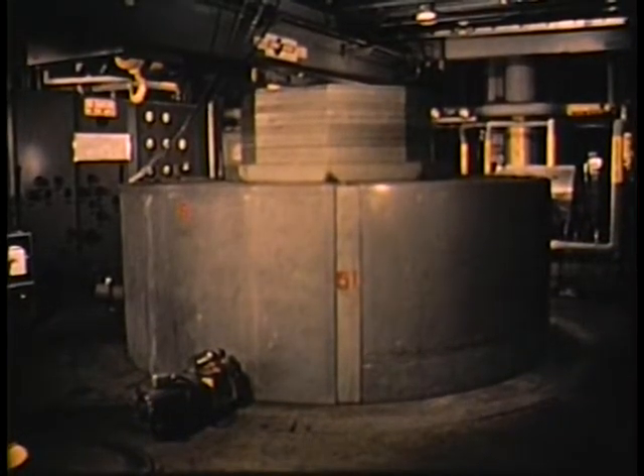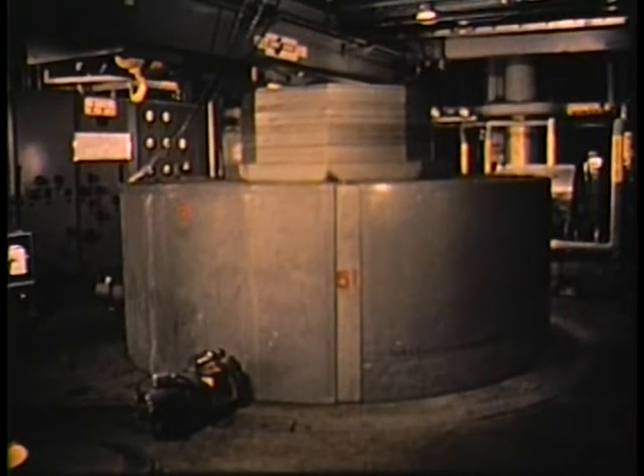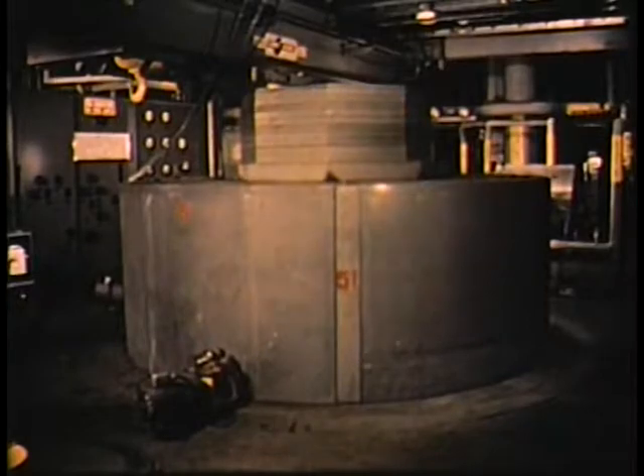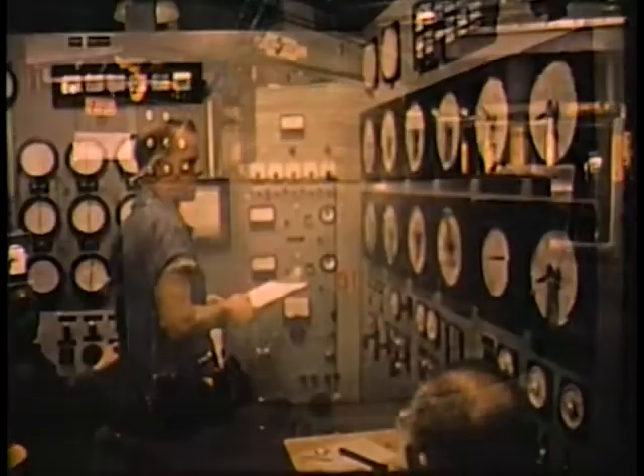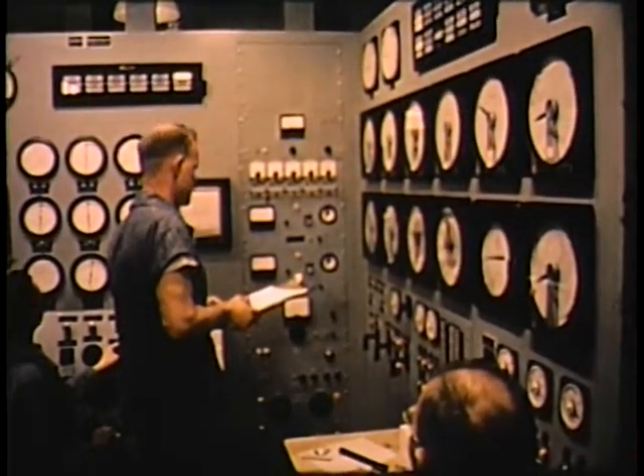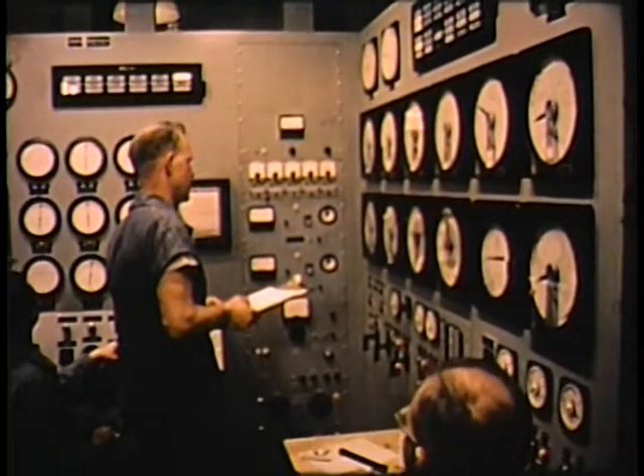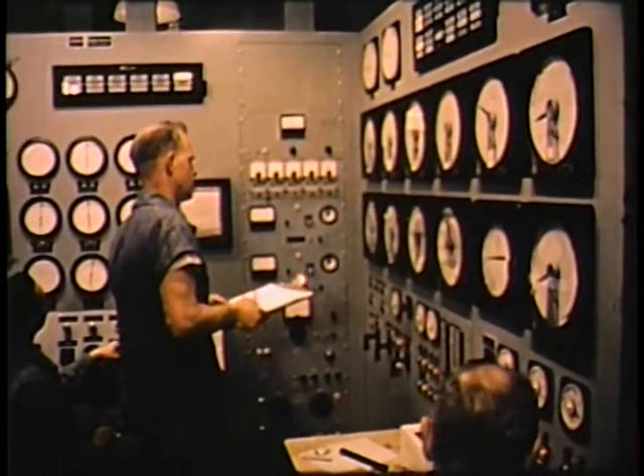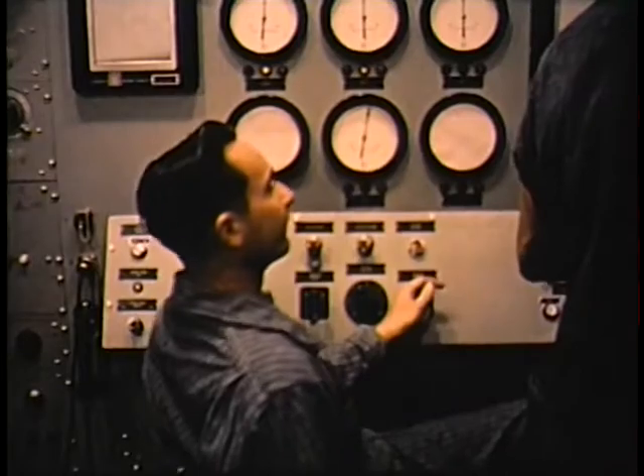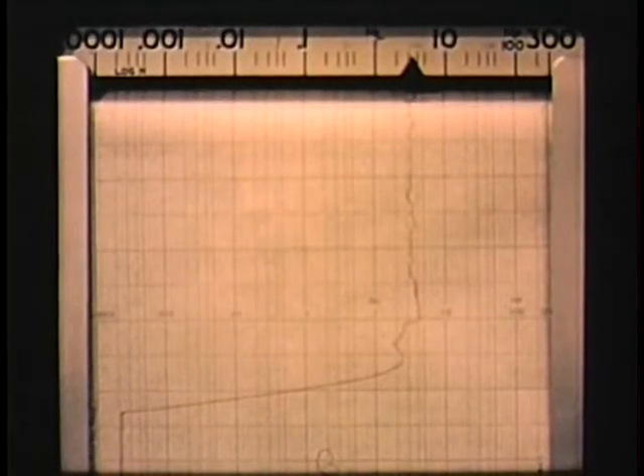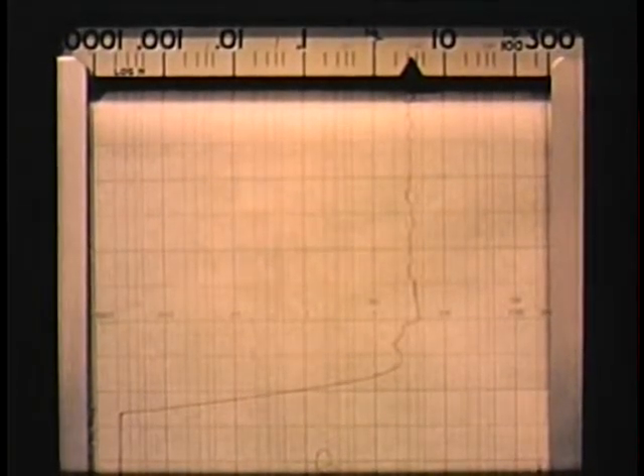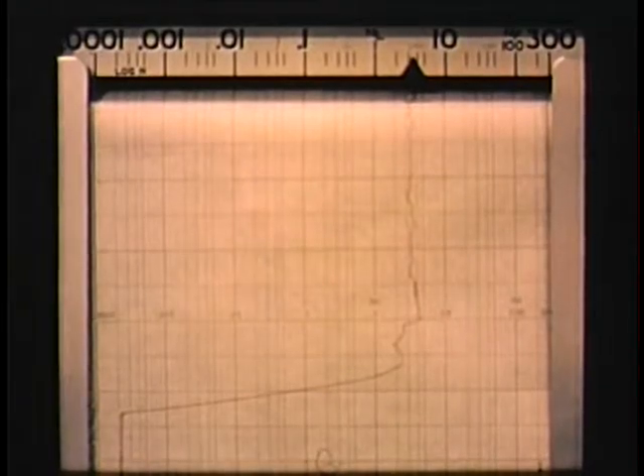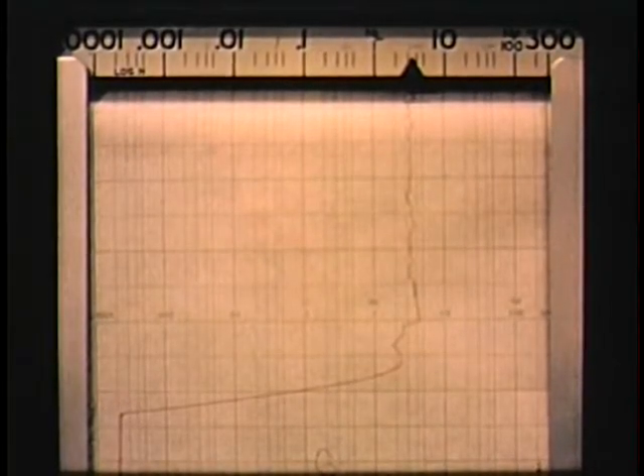On October 23, 1958, shield blocks were positioned and the reactor was brought to temperature and pressure by nuclear heating for the first time. The reactor power was raised until approximately 8,000 pounds of steam per hour was being produced. After a brief period of testing, it became evident that reactor operation was quite stable.